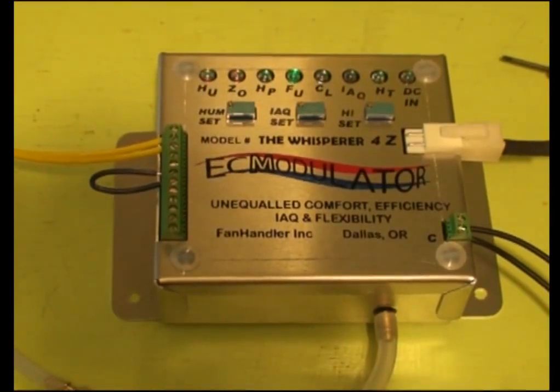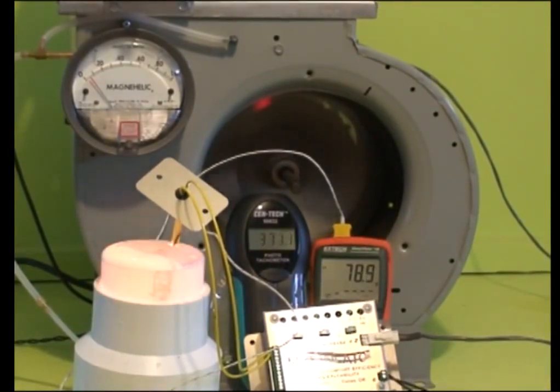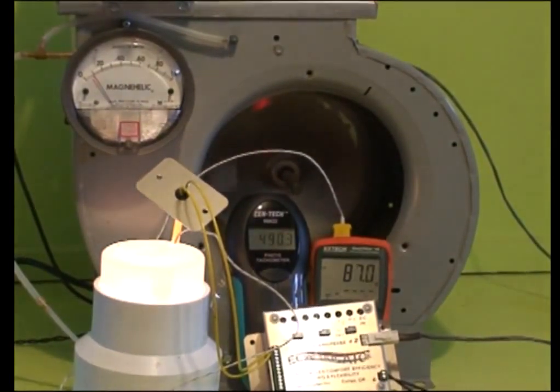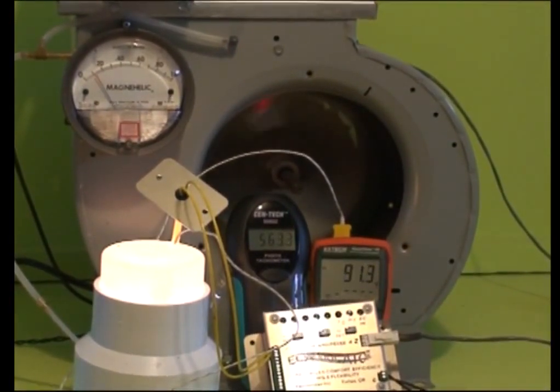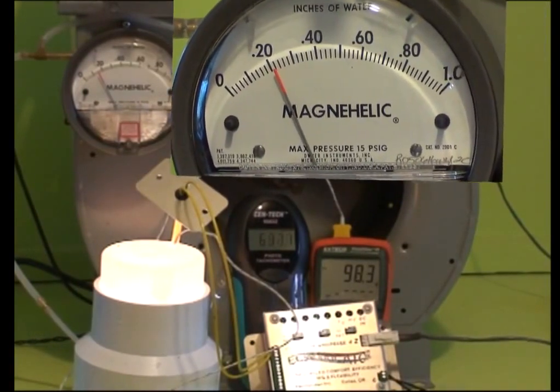In the next clip, we'll start a new temperature fan speed cycle to test our setting. Again, as the temperature builds up, the blower speed and the duct pressures increase. The duct pressure should top out at about 0.2 inches and stay there regardless of the rising duct temperature. Is that good or what?